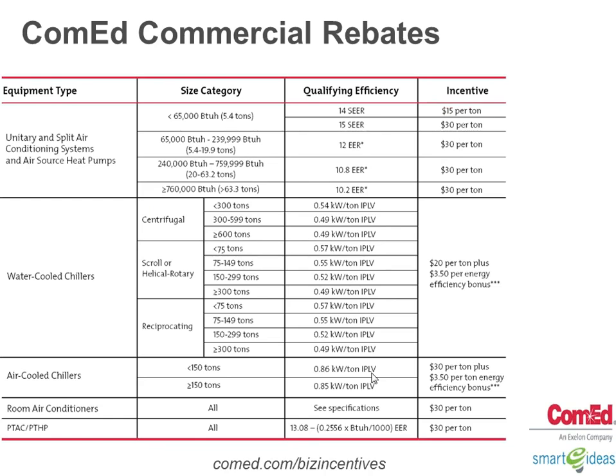IPLV is the chiller definition for what would be a part load scenario. So for this rebate program, they do not look at the full load operating efficiency of the chiller. The full operating efficiency is fairly irrelevant because you're only going to be at that point for less than 1% of the year.